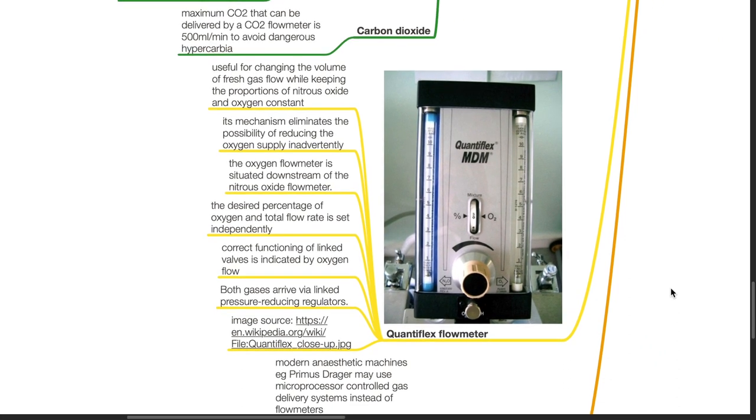Quantiflex flow meter: It is useful for changing the volume of fresh gas flow while keeping the proportions of nitrous oxide and oxygen constant. Its mechanism eliminates the possibility of reducing the oxygen supply inadvertently.